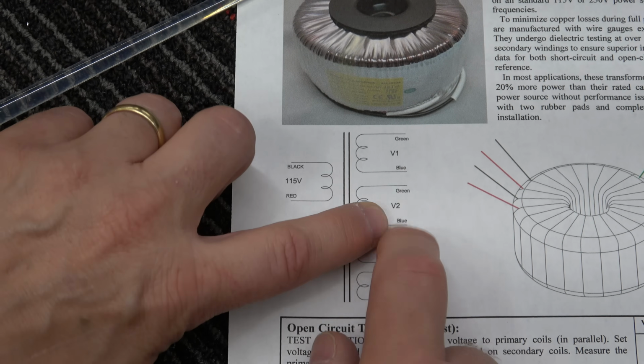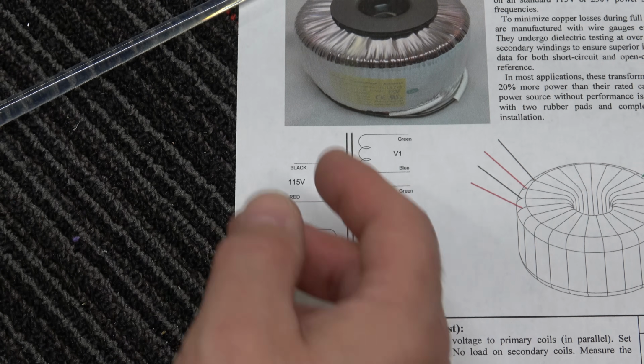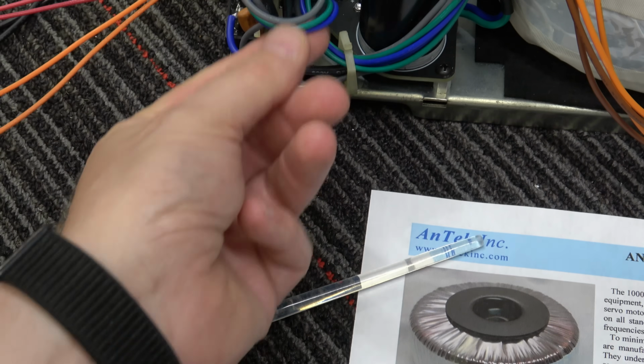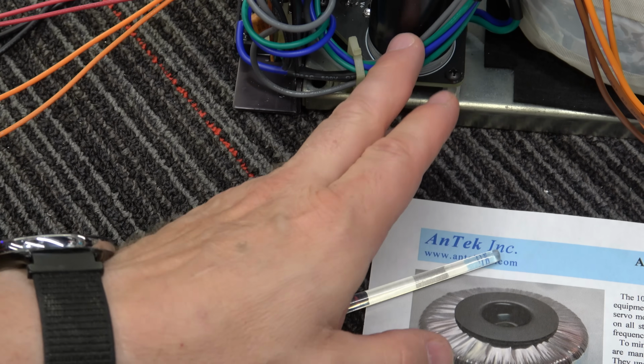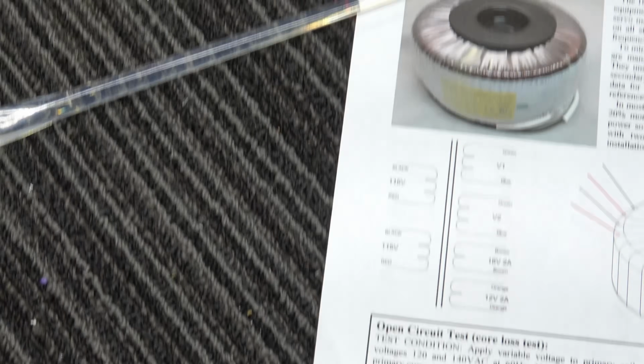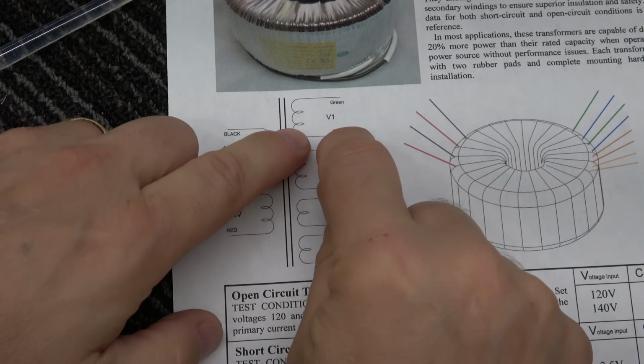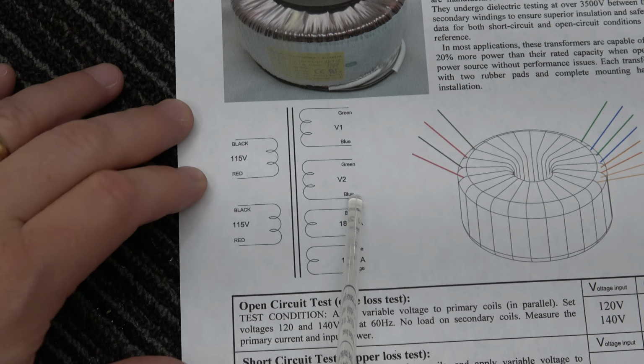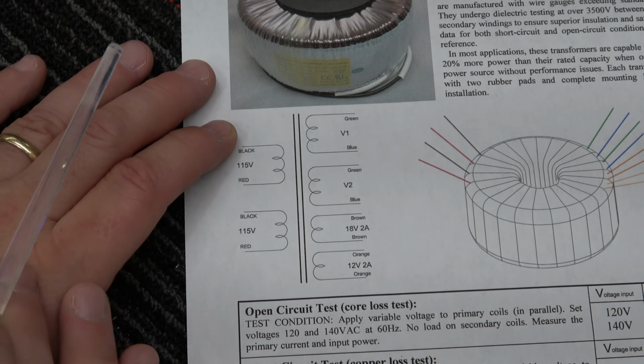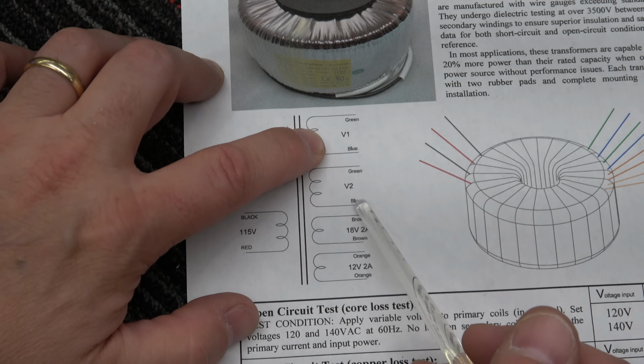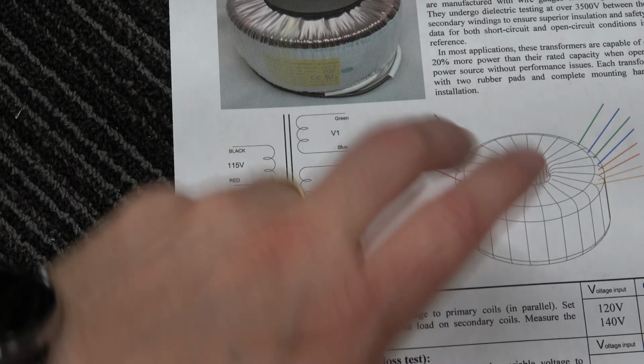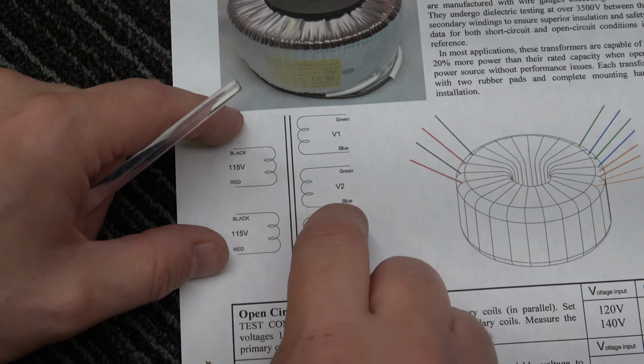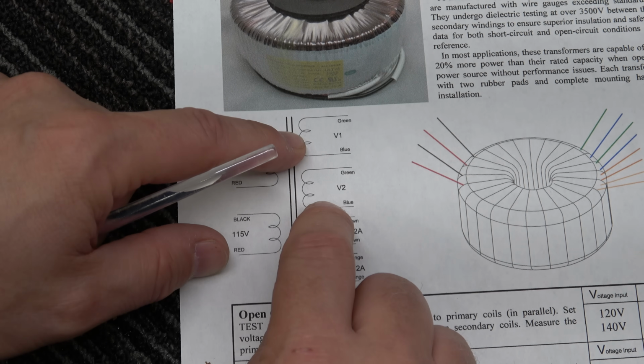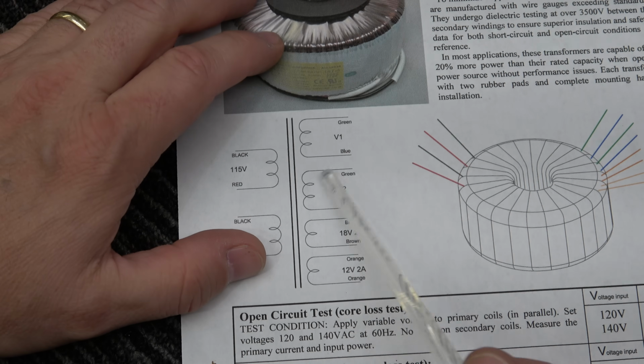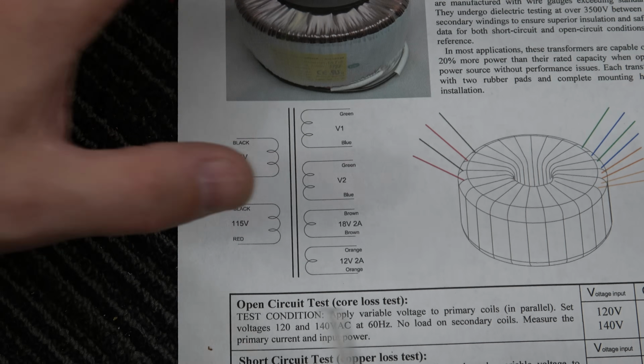They're covering the same spot on the core but are not electrically connected. Looking here, you have the blue wires and the green wires, two blues and two greens. The blue wires represent one end of each coil, the green wires the other end of the winding. These two blue wires were right next to one another on the core, so I unwound this side from both of them equally, which makes both the same voltage and the same physical length.